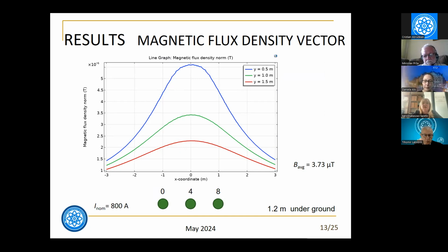We made the calculation on 3 heights, on 3 levels, where the 0 level is on the ground surface. And as we can see, the biggest value is at the nearest distance from the ground level, and the maximum value is about 5 microtesla. Calculating the average value of the magnetic flux density vector at these three heights, we calculated that it is 3.73 microtesla, which is much below the 40 microtesla from the domestic regulation.